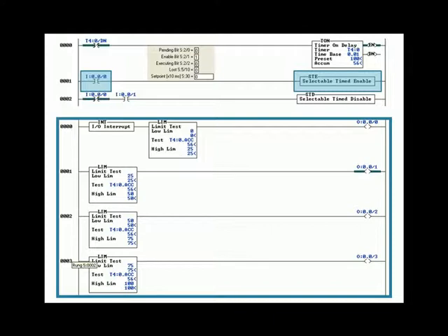That's because when I did this screen capture, the interrupt was disabled. I had left ladder 5 in this state, but the timer keeps on running. The timer is in ladder 2, not in ladder 5. That's another interesting thing to make note of. T4:0 runs continuously in ladder 2. Ladder 5 only gets executed when the selectable time interrupt is enabled. So if I disabled it when, we'll say it was at 30, well, output 1 would be on, but T4:0.ACC would keep accumulating because you're displaying the value in the timer register, and the timer instruction is in ladder 2.